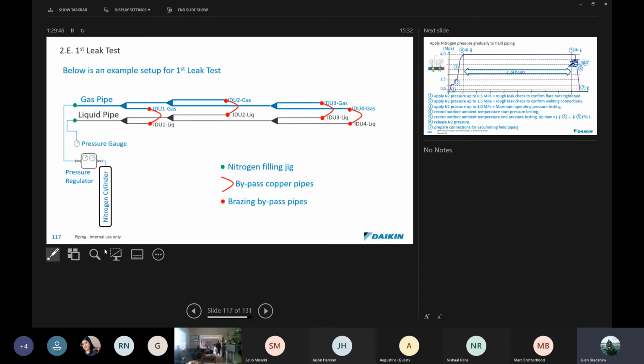So when we're looking at this over here, we're looking at that type of arrangement. We've got gas and liquid pipes. They've looped out the piping just temporarily, and they've pressurized just this piping for the indoor units, without the indoor units connected. Then they will leave this on, and they'll be able to tell any leaks in there. They're only looking for a gas leak or a leak in that section of piping.